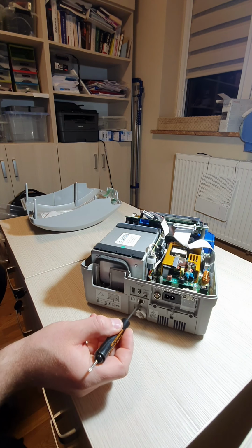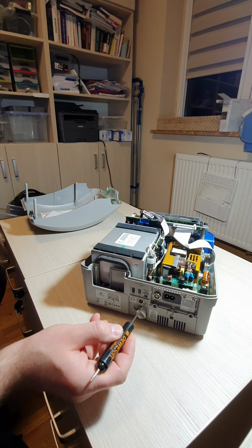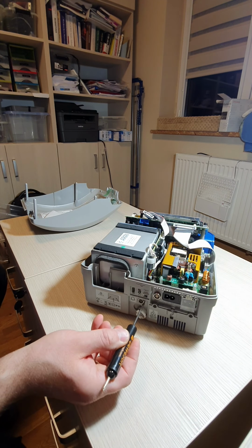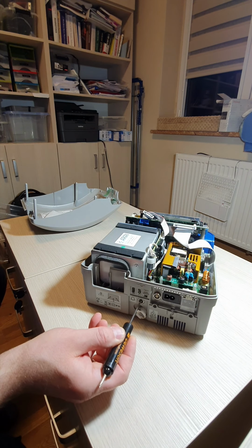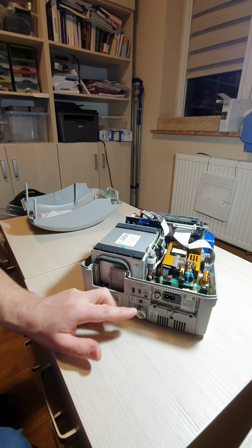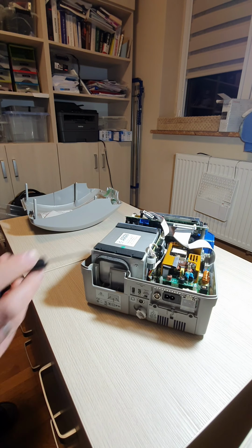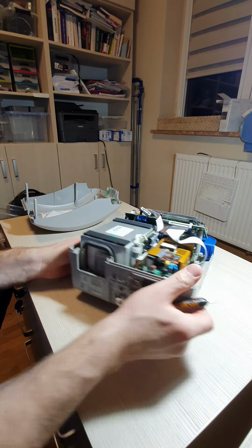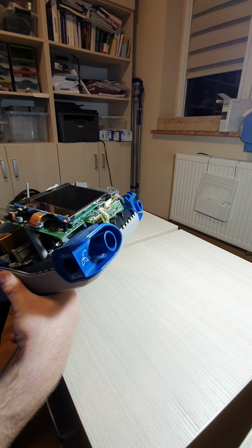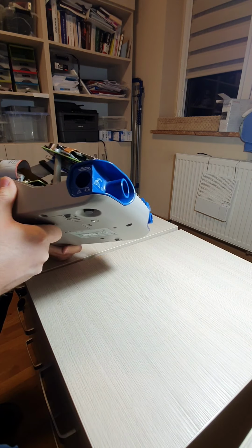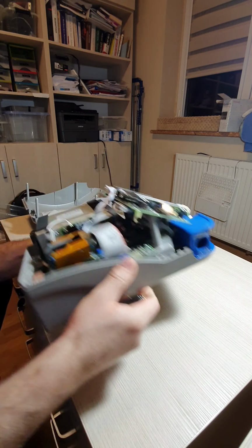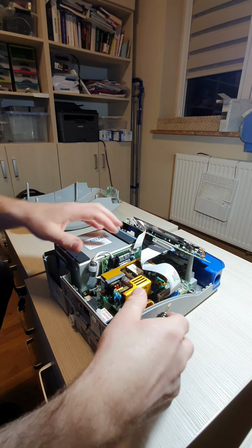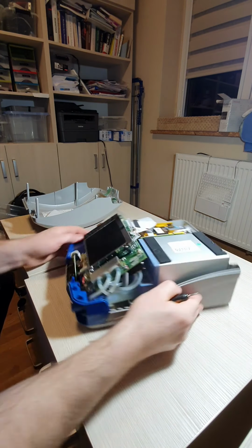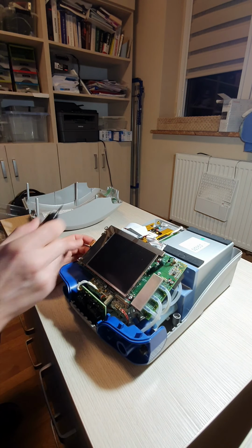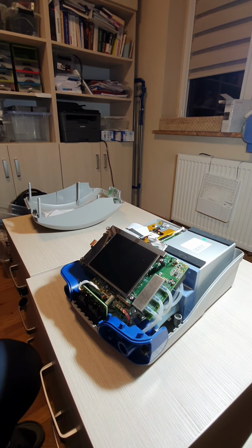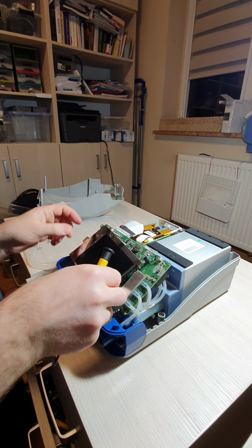It is also possible to connect a wireless extender. So instead of connecting the cable to the ventilator directly, one can extend the range by putting a similar small box with a similar connector somewhere else, and this ventilator will communicate wirelessly. There should be a wireless module somewhere here, but it's open. Let's remove the panel, we'll see maybe. So let's remove the turbine. The turbine is under the LCD screen. So I remove the screws.